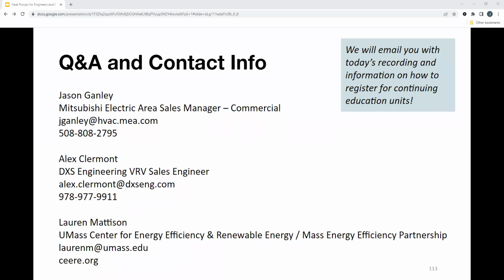Yeah, I can do the first one. I've run into instances on large commercial VRF installs which cannot prioritize itself as a second stage to a hot water or chilled water valve through proprietary controls, so that should be investigated prior to a specification process. To answer that question, you still are able to integrate heat pumps as a second stage. You do need a certain dual stage controller. This would be a third-party device that you can add on, where you have all the contacts necessary for that.